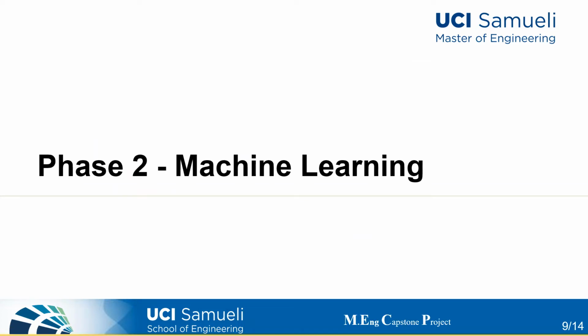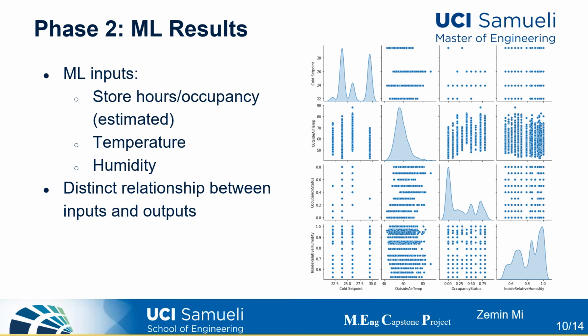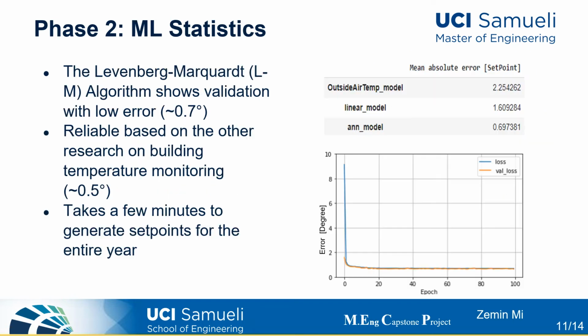Phase 2. Machine Learning. Here are the machine learning results. The inputs of the machine learning include the store hours, the occupancy, which is estimated, temperature, and humidity. On the graph on the right side, we can see the distribution of the inputs with the set points. The machine learning model shows validation of the LM algorithm by the low error, which is down to 0.7 degrees, compared to the linear model and temperature domain model, which are 1.6 degrees and 2.2 degrees respectively.